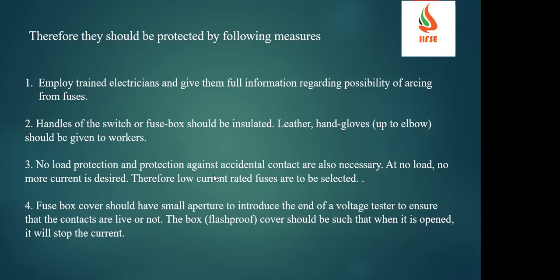Therefore, there should be protection through the following measures. Definitely we'll have employees trained as electricians and give them full information regarding the possibility of arcing and the fuses. Handles of the switches or fuse box should be insulated, and leather hand gloves and rubber hand gloves have to be provided to avoid electric shock. No load protection and protection against accidental contacts are necessary. At no load, no more current is desired, therefore low current rated fuses are selected. So whenever you are putting in low current fuses, what will happen?